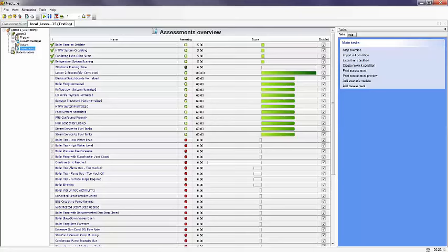What will cause a critical error? Trip the boiler, and this is basically a low level. Trip the boiler on a high. Boiler pressure rise excessive, in other words, you haven't dropped down to a minimal firing rate. You have to drop down to a minimal firing rate because you would damage this boiler if you didn't. Firing this boiler with the superheater vent closed. Again, we're worried about that superheater vent. Even though in the beginning like this, it would not physically hurt it because you're not producing steam, it's still protocol. Any chief engineer that I know of out there would have your guts for garters if you lit off this boiler without opening the superheater vent.